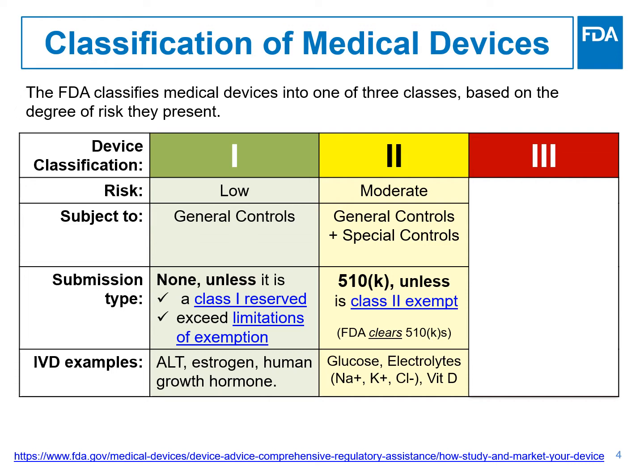FDA classifies into Class 2 devices with moderate risk, for which general controls alone are insufficient to provide reasonable assurance of safety and effectiveness, and for which there is sufficient information to establish special controls to provide such assurance. Special controls are usually device-specific and may include things like performance standards, post-market surveillance, special labeling requirements, pre-market data requirements, among others. Most, but not all, Class 2 devices require a pre-market notification that is known as 510K.